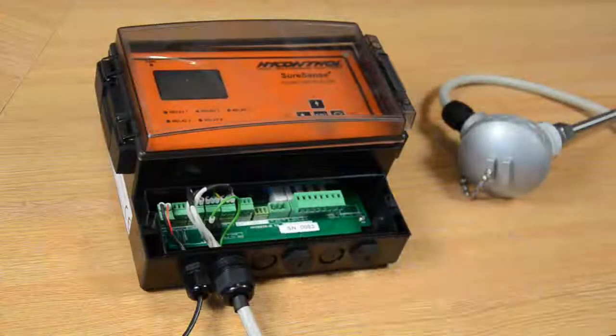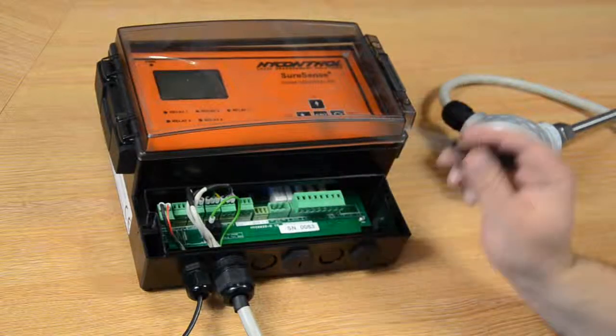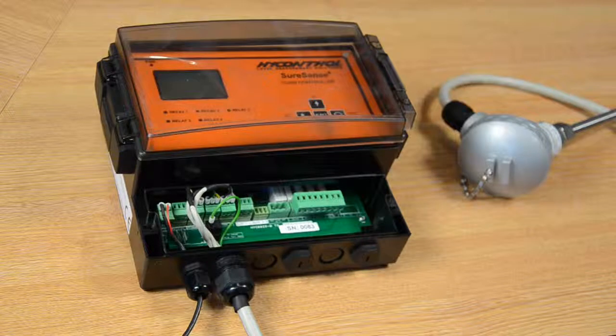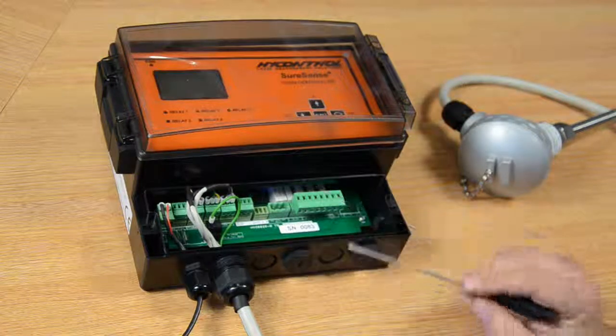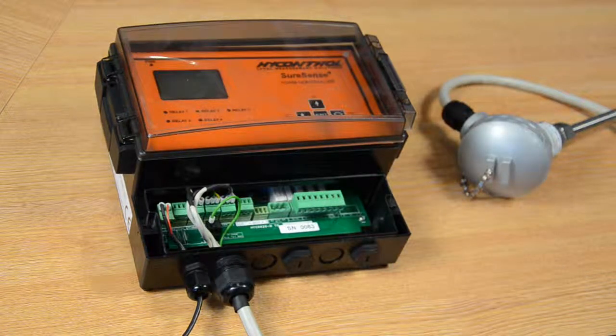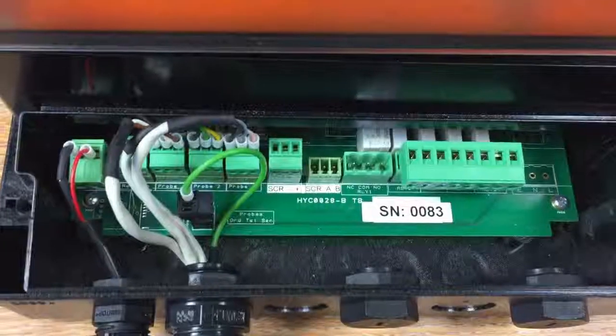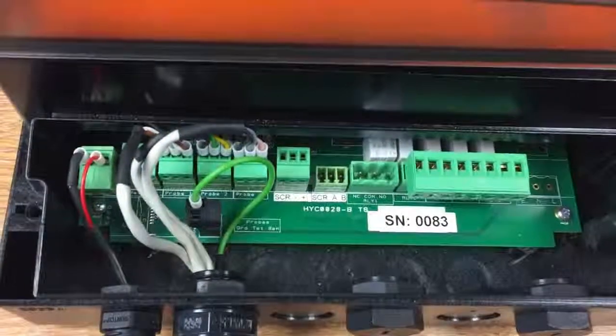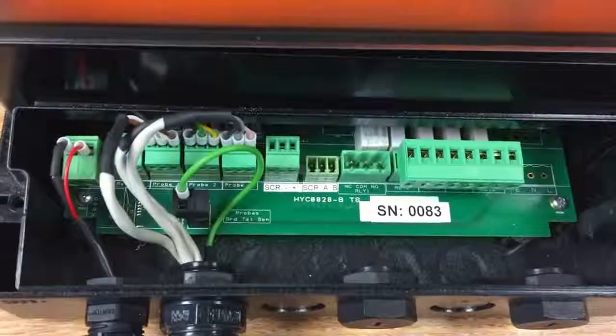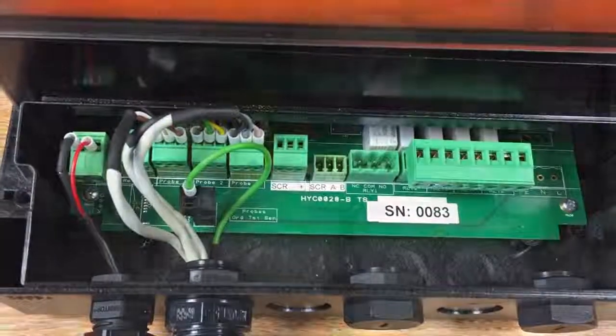So now your system's wired up, you'll be able to detect foam and the controller will show you when it's there. It'll also be able to detect liquid, but we haven't set any outputs up yet. So to do that, we'll use either our 4-20 or our volt-free contacts. The volt-free contacts can be used to control dosing pumps, to activate alarms, to actuate solenoids. You can even have the 4-20 back to your PLC. There are instructions on how to wire all your outputs up in the manual. If you need any help setting this up, don't hesitate to give us a call.